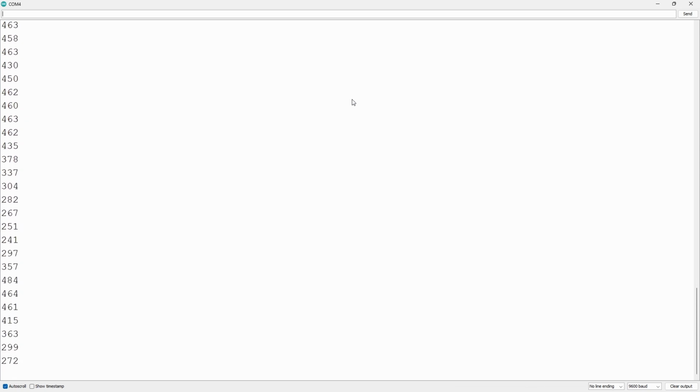The second problem you're going to encounter is that when you draw the sensor out of the water, you're going to find that there's still some water on the surface. This is going to give a reading and make your results inaccurate.